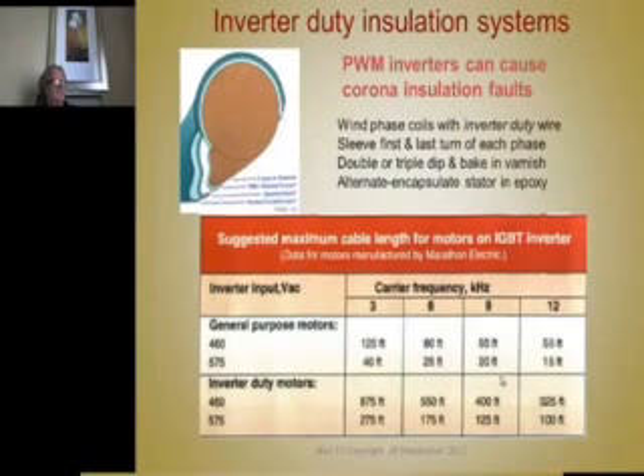Well, if your motor has the inverter mounted a long ways away, you've got to deal with this. And the first thing you do is use magnet wire that's been developed that has insulation that resists these failures. These insulation materials don't eliminate it, they just increase the life a long time. A lot of motor manufacturers will use this inverter duty insulated magnet wire.